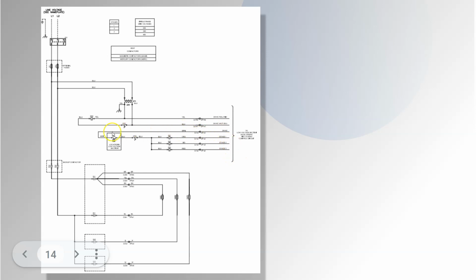Now, I like it when boxes do this because different manufacturers of different controls either send out a 24 volt hot or 24 volt common signal. Johnson Controls on the VAV units, on the binaries, actually need to send out a common. So we would put our hot right here and we would close the commons. Some other controls, or even older Johnson stuff, used to switch the hot. In that case, we would need to put the 24 volt common right here on the 24 volt AC, and we would fire the hot. So depending on the different control manufacturer is how you would wire that up.